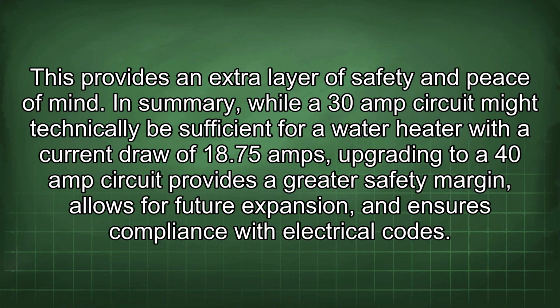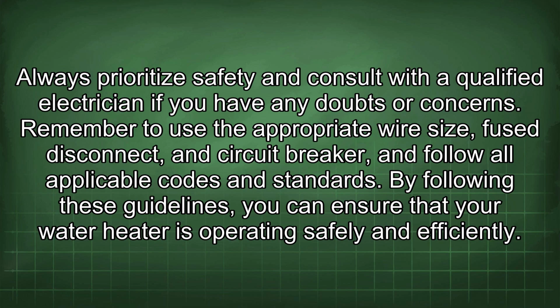In summary, while a 30 amp circuit might technically be sufficient for a water heater with a current draw of 18.75 amps, upgrading to a 40 amp circuit provides a greater safety margin, allows for future expansion, and ensures compliance with electrical codes. Always prioritize safety and consult with a qualified electrician if you have any doubts or concerns. Remember to use the appropriate wire size, fuse disconnect, and circuit breaker, and follow all applicable codes and standards. By following these guidelines, you can ensure that your water heater is operating safely and efficiently.